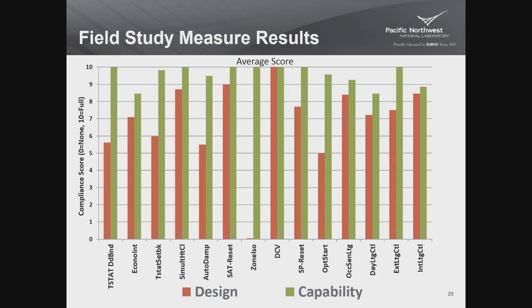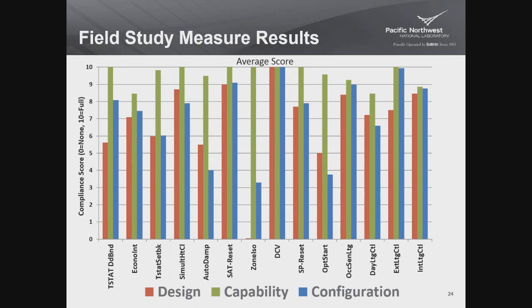So then if we now look at the configured perspective, you can see, of course, it's quite a bit lower. So even though they had the capability, they were not configured to operate according to the control requirement. And we also found that buildings that had the requirement in the design were more likely to have it configured that way as well. So you can see it in all cases lower than the capability score. It has to be. In most cases, the configured score was lower than the design score, but not always. And we're going to look at some of the same data in a few different ways just to give you some different perspectives on it.